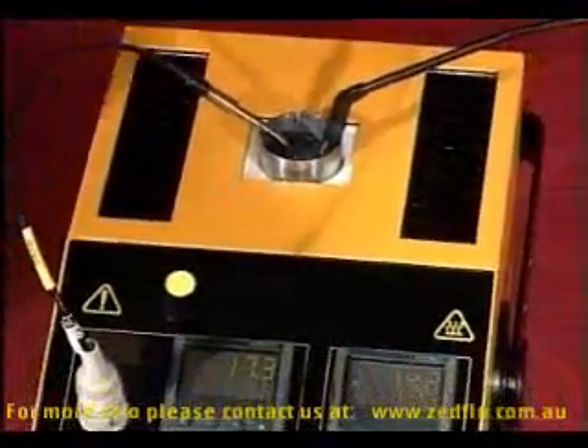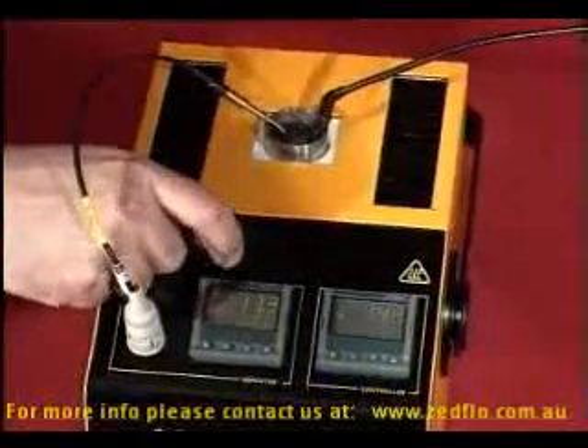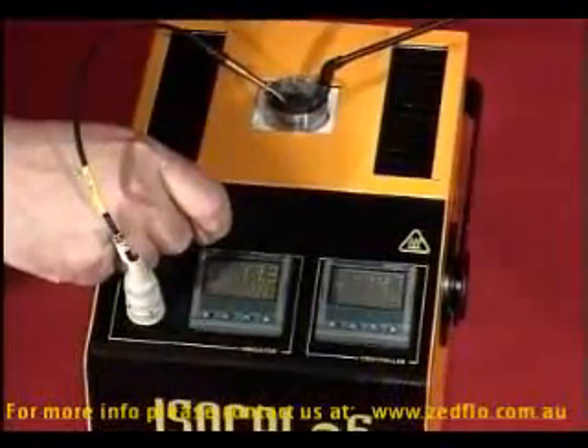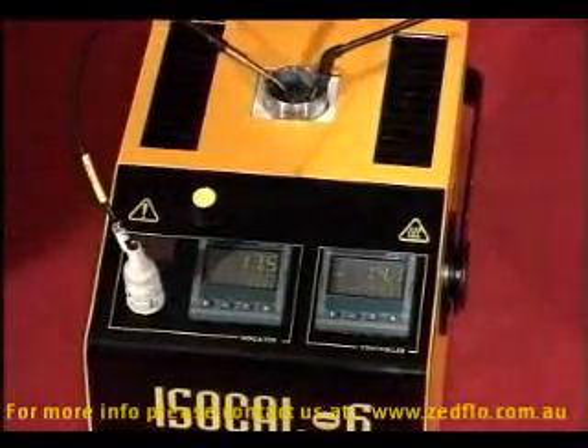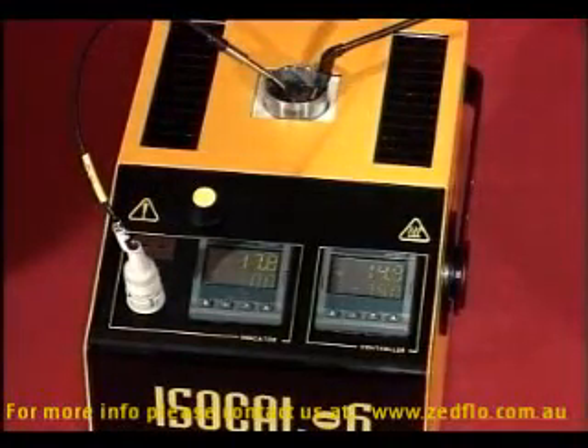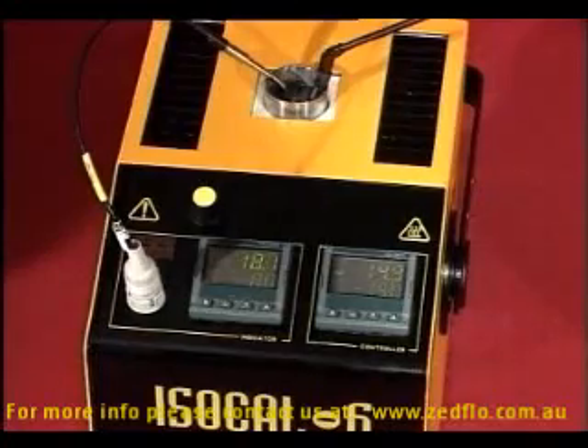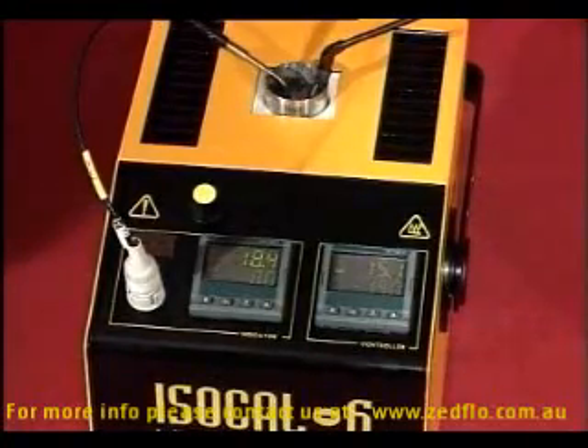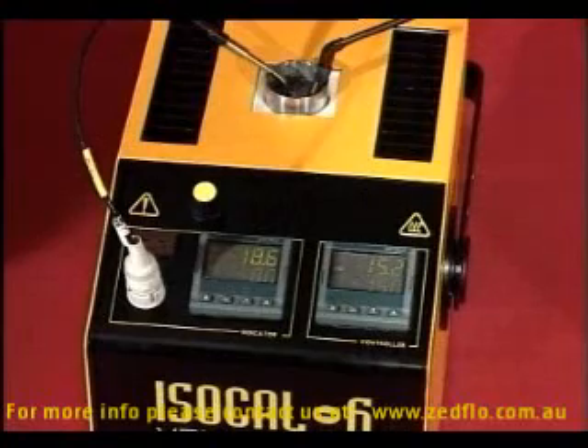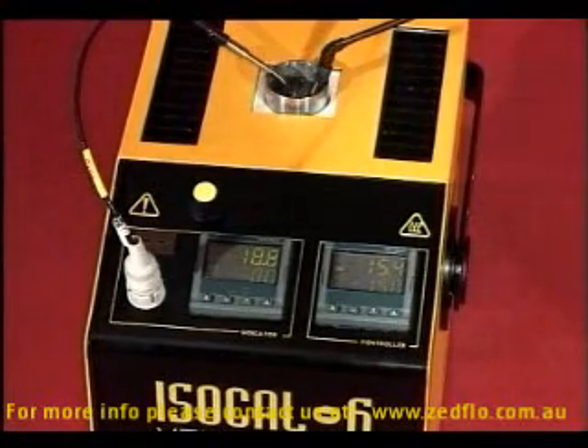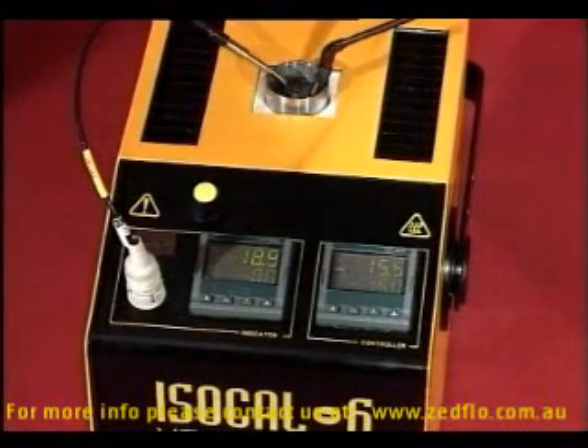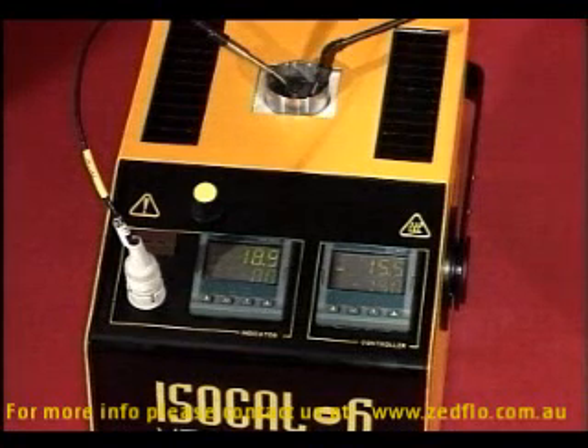You can see here a yellow knob. Turn this clockwise first and it switches on the stirring motor. Then it controls the speed of the stirring motor. This stirs the liquid in the liquid bath at different speeds, depending on the viscosity of the liquid being stirred. This gives you constant volume of liquid with a great deal of homogeneity, both vertically and horizontally, for the calibration of odd-shaped sensors and short sensors. Let's now have a look at some of the characteristics of the stirred liquid bath option of the Isocal 6.